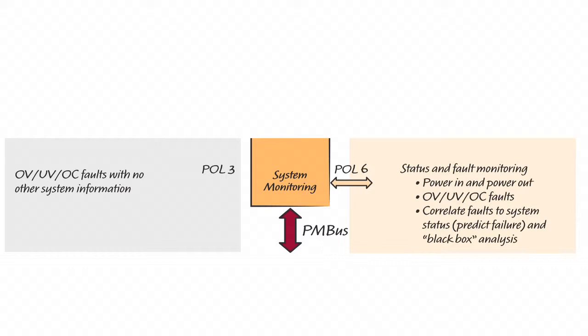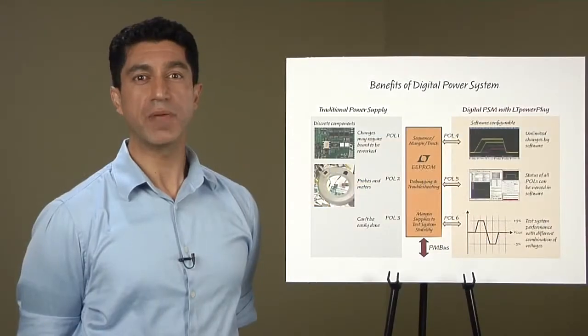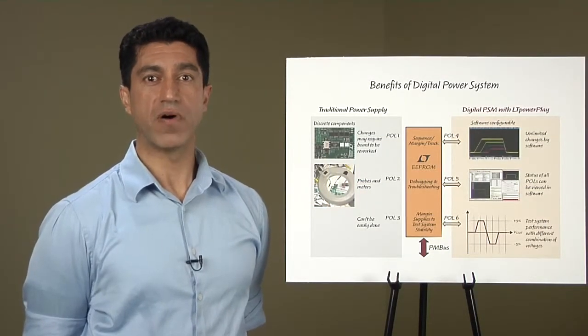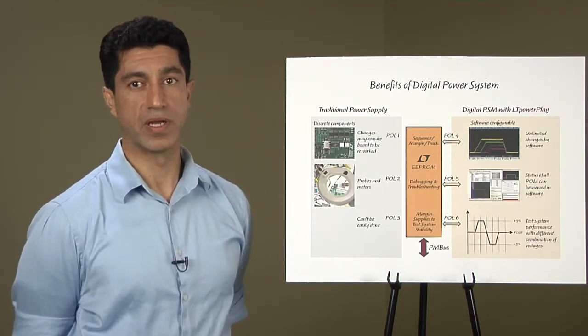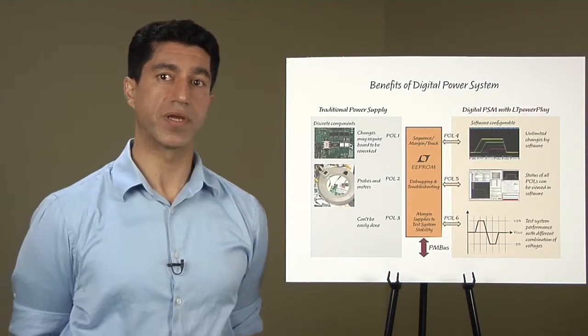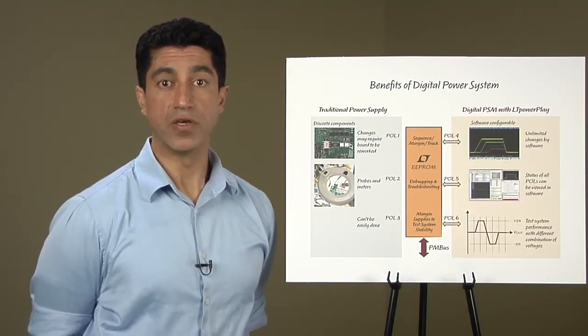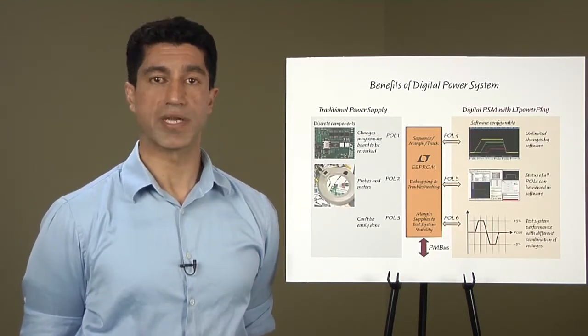In the digitally managed power supply, power monitoring functions are built-in and are programmable. Fault conditions for one POL can be easily combined with other POLs to create a customized response to a variety of fault conditions. With a digitally managed supply, detected faults are correlated with high-accuracy measurements of voltage, current, and temperature. Internal, non-volatile memory can store the information useful for debugging and root cause analysis.